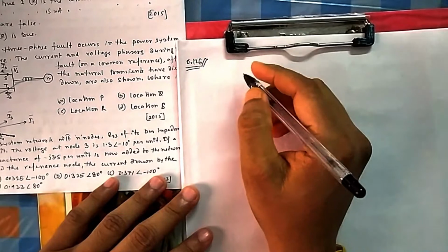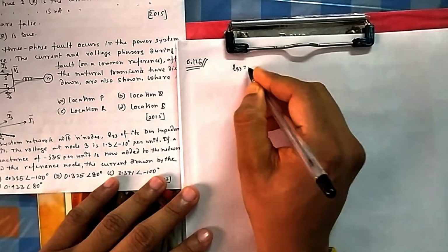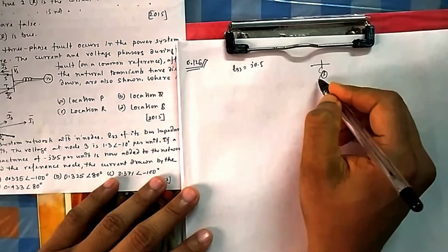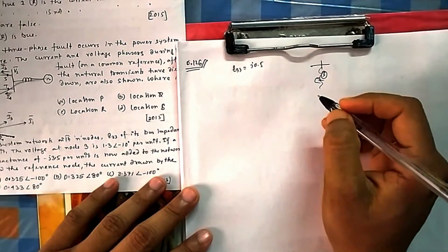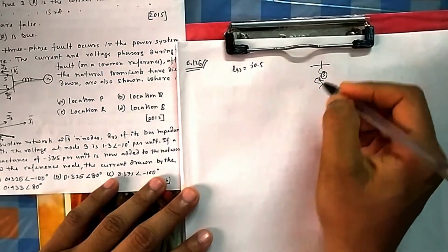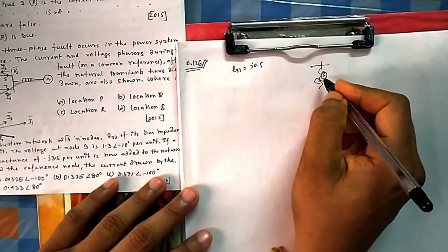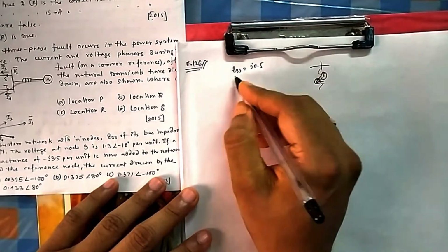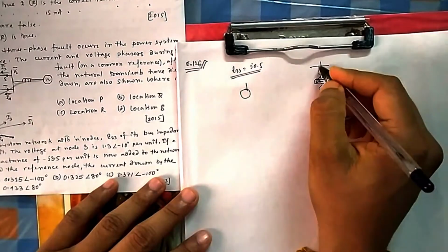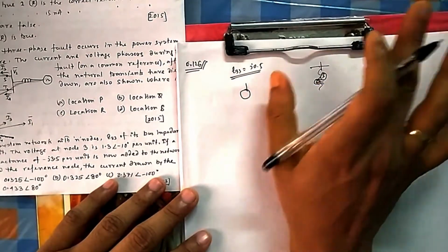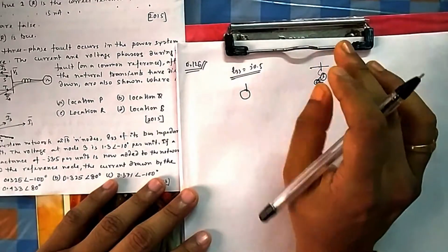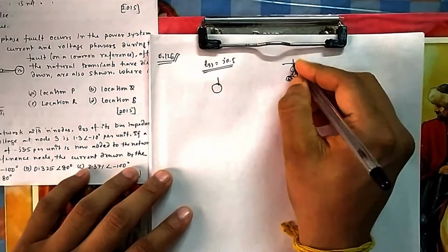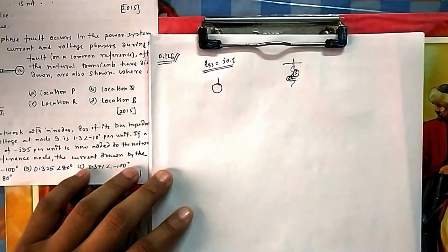Suppose I look at Z33, they have given 0.5. That is, if you look from bus 3, what should be the Thevenin's equivalent? For fault analysis, that's what we do in three-phase fault analysis: from that bus we look around and see what the Thevenin's voltage is. My system voltage is always treated as pre-fault voltage; in load flow, and in fault calculation, the pre-fault voltage of the bus where the fault is occurring is taken as 1 per unit.